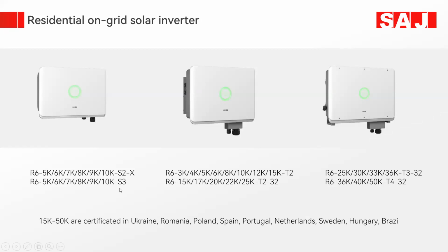S3 means single phase and 3 MPPTs. When we talk about three phase, we have 3 kilowatt to 15 kilowatt as per every country's requirement. We have a T2 in the three phase. T means three phase and the 2 means 2 MPPT. When we talk about the R6 15 kilowatt to 25 kilowatt, we have T2 32, three phase, 2 MPPT and 32 amperes maximum rating per MPPT. Then R6 25 kilowatt has a T3, three phase and 3 MPPT. Every MPPT is 32 ampere rating, and 36 kilowatt to 50 kilowatt is T4.